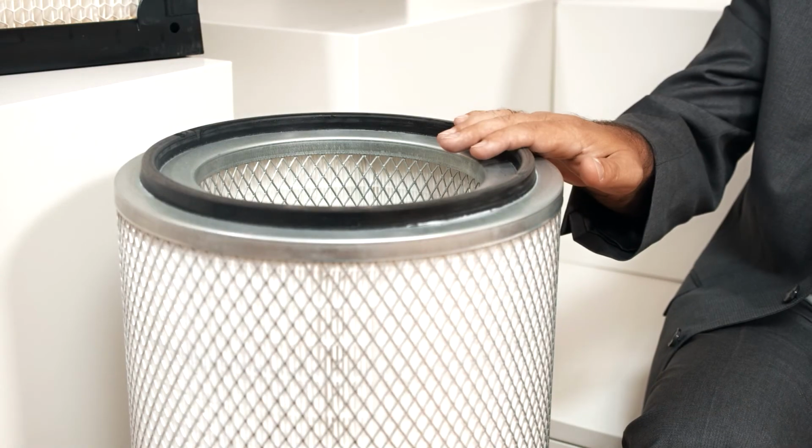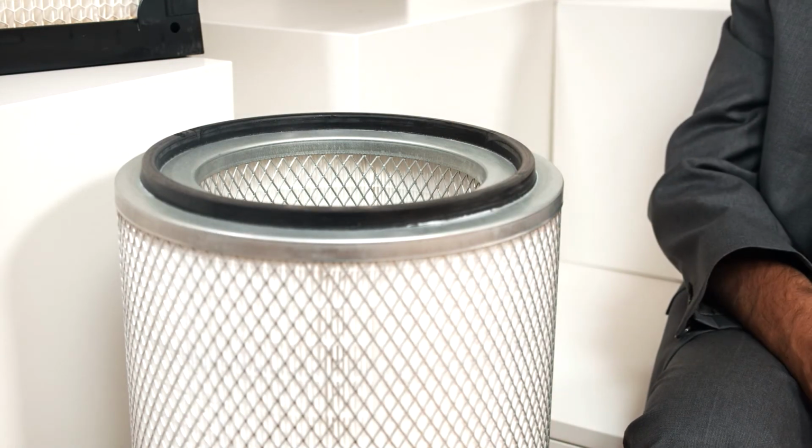The standard is primarily written for static filters like panel pre-filters, pocket filters and rigid filters. What is new is that the standard also specifies how round filter elements can be installed in the test bench and how the static efficiency of such elements can be tested.